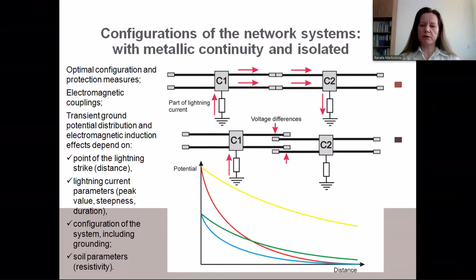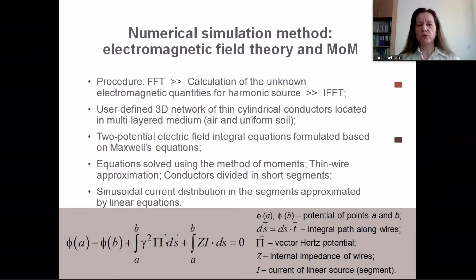The system is represented by a three-dimensional structure composed of thin cylindrical conductors divided into short segments located in a multi-layered medium. The two-potential electric field integral equations formulated based on Maxwell's equations are solved numerically with the method of moments. The system under study is composed of two controllers, each supporting two cable sensors. Along the transition detection zone, a lighting system is usually installed. It was assumed that the lightning strikes the lighting pole nearest to the controller C1. The lightning current is represented by the standard recommended waveform with 100 kiloamperes peak value, and this current flows into the horizontal grounding electrode of the lighting system.